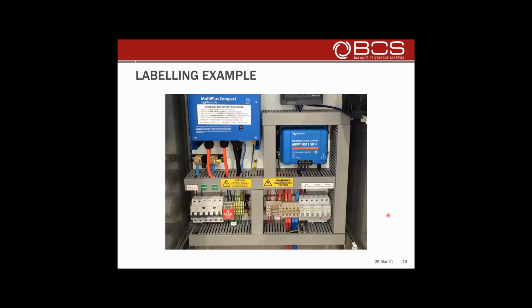And a labelling example. In this instance, we're using ductwork with all the cable, but yeah, each circuit breaker is clearly labelled, as well as warning labels. Obviously in Australia, we must have very specific warning labels for AC power sources, DC power sources, and where batteries are installed, things like this.